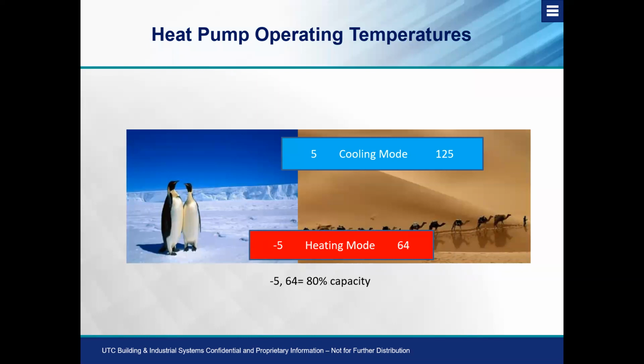Of course, this all varies based on combinations that we have hooked up to the outdoor unit. And then, of course, whether we're dealing with a 6-ton system or a 12-ton system or a 20-ton system, and how we have those units twinned, tripled, or whether we have a single module, will essentially dictate how much coil surface area we have, and also how many compressors we have in that system to add redundancy and also low ambient heating capabilities. And then again, these are just rated performance ratings. The systems will run below this. Of course, they will naturally derate, but these are guaranteed performance ratings.